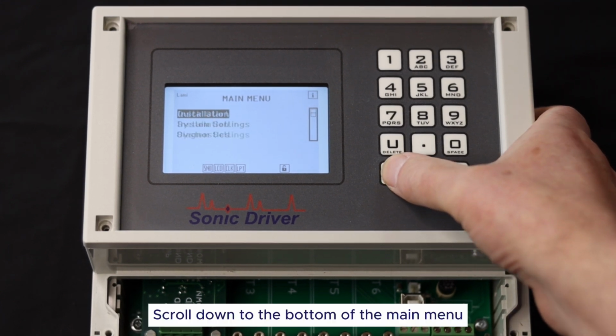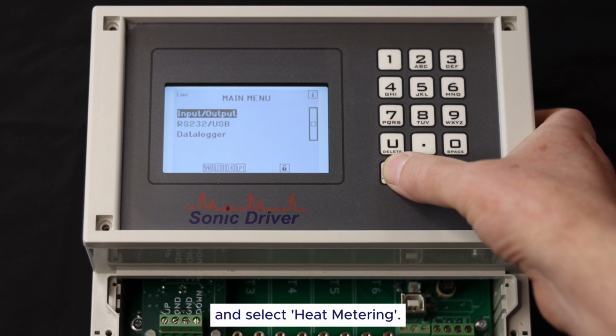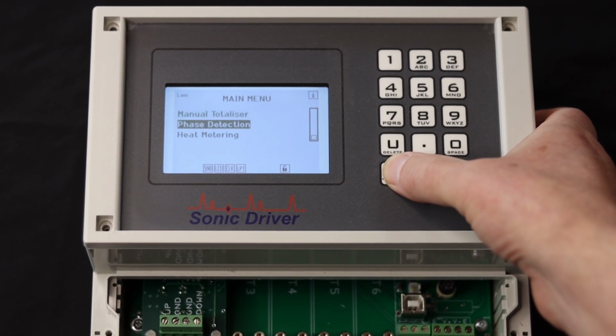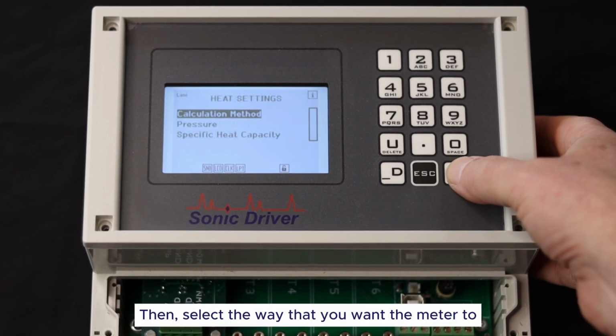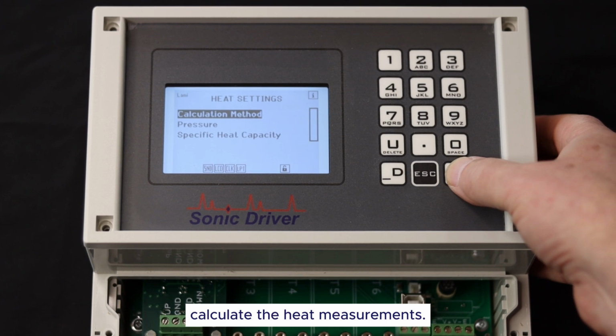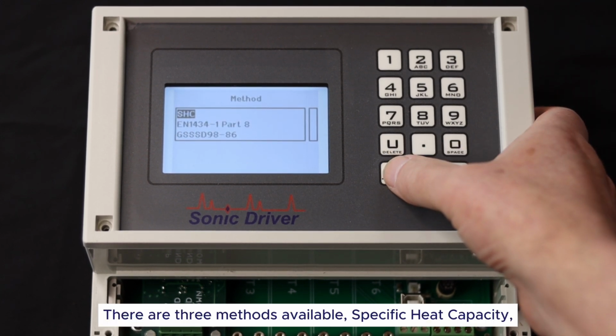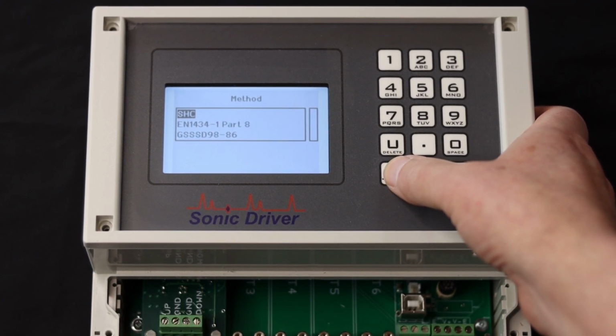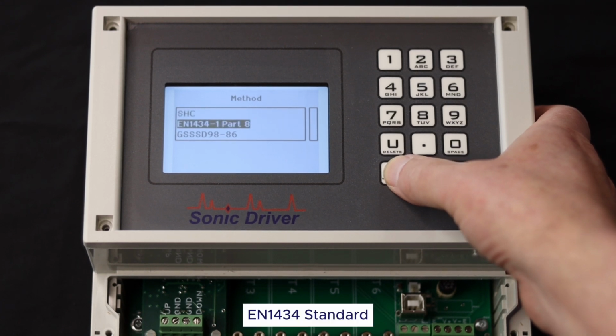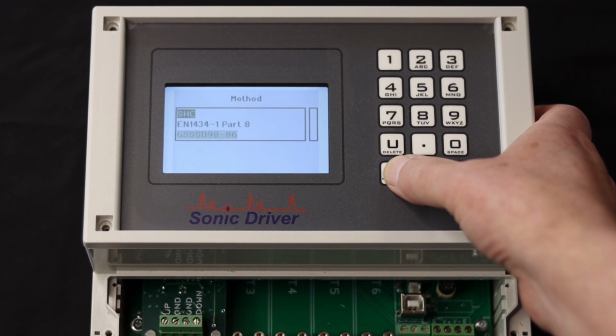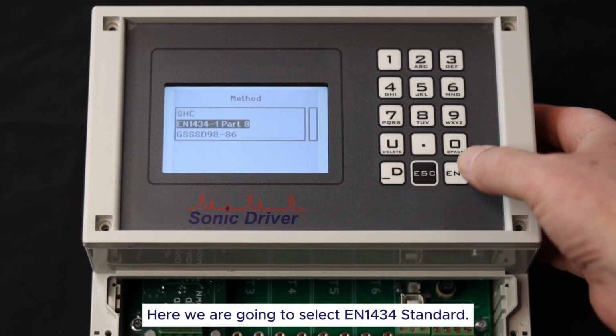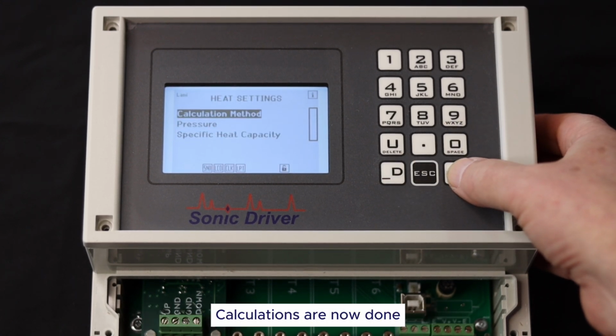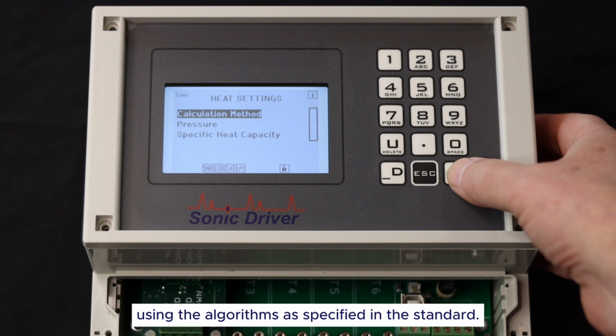Scroll down to the bottom of the main menu and select Heat Metering. Then, select the way that you want the meter to calculate the heat measurements. There are three methods available: specific heat capacity, EN1434 standard, and Russian standard. Here, we are going to select EN1434 standard. Calculations are now done using the algorithms as specified in the standard.